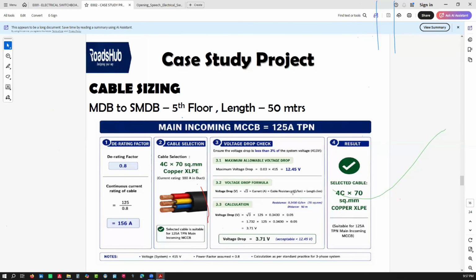We have so many formulas considering different parameters. This is just one of them. If you have very sensitive buildings, we go into including reactance. That is the R value and X value. So it depends. We have a residential voltage drop formula, we have commercial, and we also have one for domestic. So once you do that, you now get a value that you can compare with the maximum allowable voltage drop. And if it's below 12.45, it is acceptable. So you've done a rating of the cable, you've tested the voltage drop, you now pick whatever value of cable, because that will be precise if it passes the voltage drop case. But if it doesn't, you go to another manufacturer, because that manufacturer will not work for you.